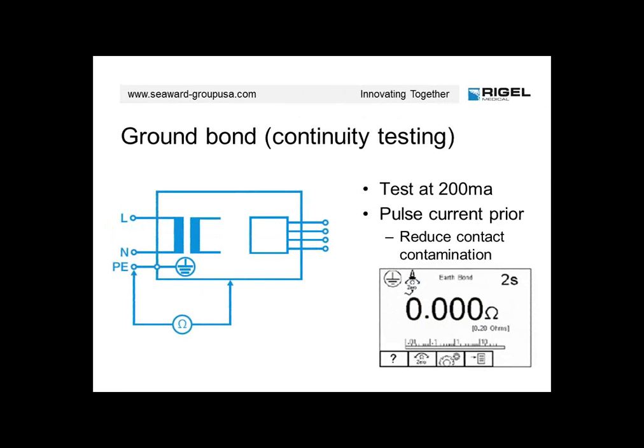So diving into the testing itself a little bit, here is the ground bond or continuity testing, as we would probably refer to it here in the U.S. Historically, this was always done at 25 amps, as specified by the 601 specification. In 62353, that is decreased down to 200 milliamps.